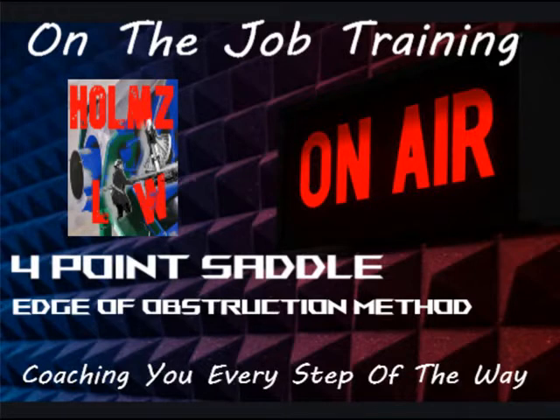Calculate, measure, and write down these 4 values, which are the height of the obstruction, the width of the obstruction, the length to the edge of the obstruction, whether it be a box that you're working from or a coupling that you're working from, to the edge of the obstruction. And lastly, number 4, the spacing between bends value. Just write those 4 down, and then right next to it, you're going to fill in the blanks as we calculate them.